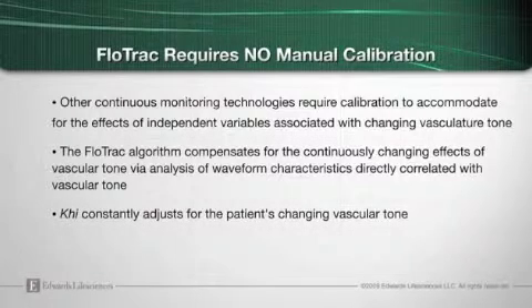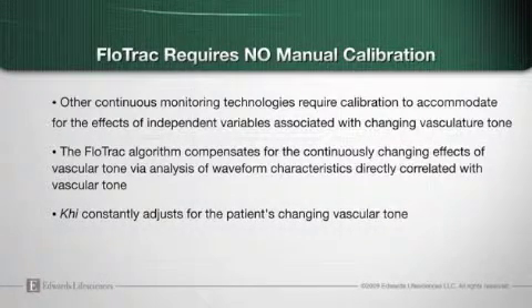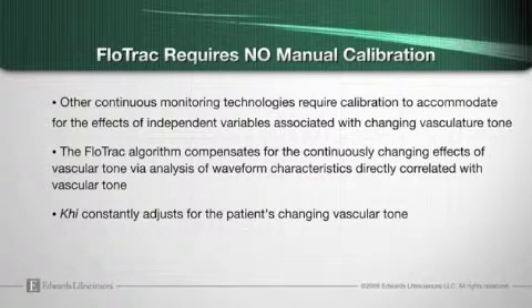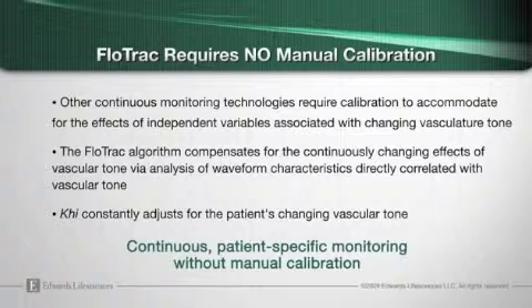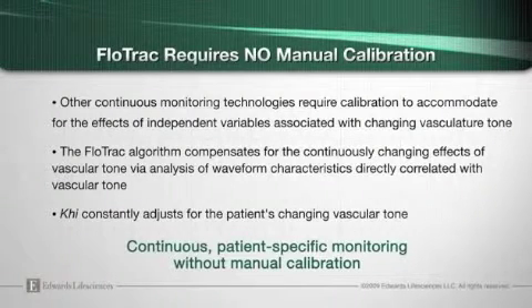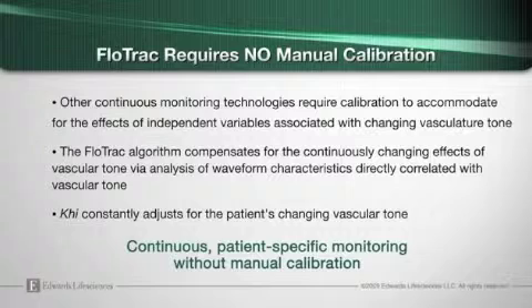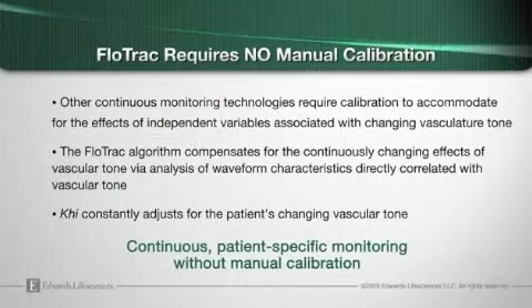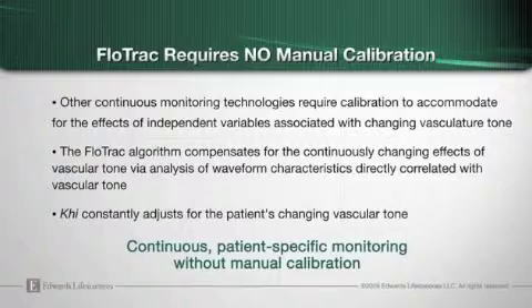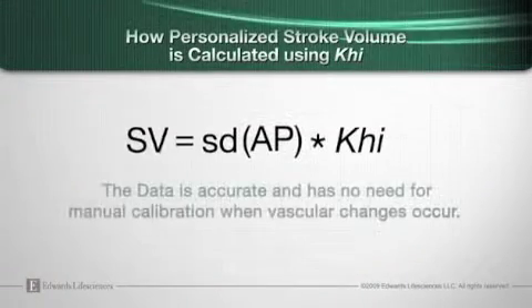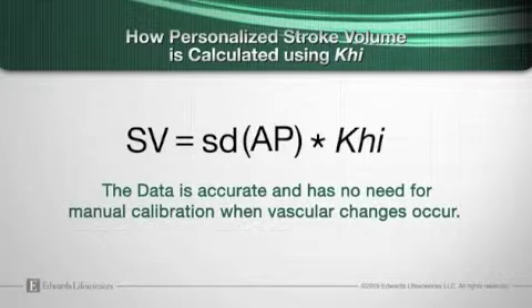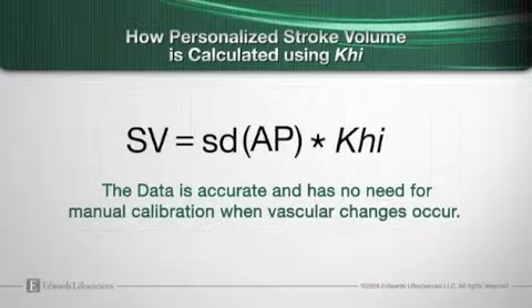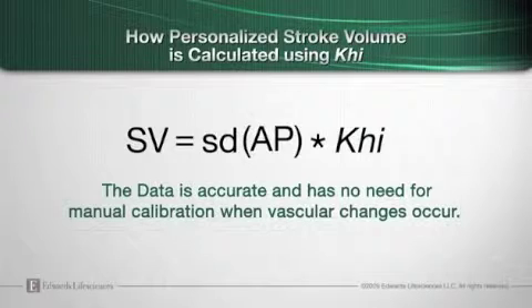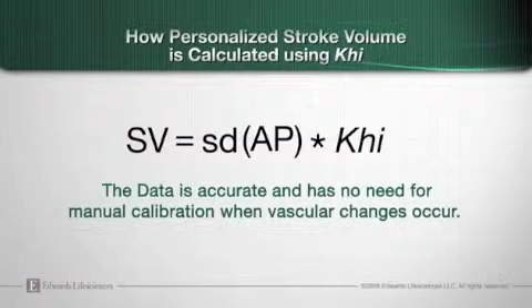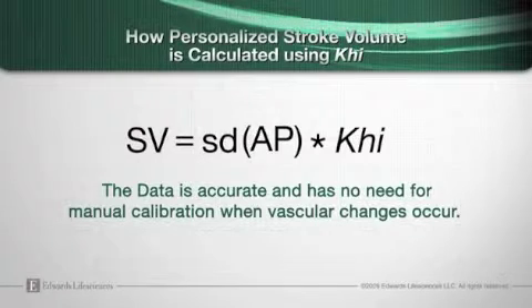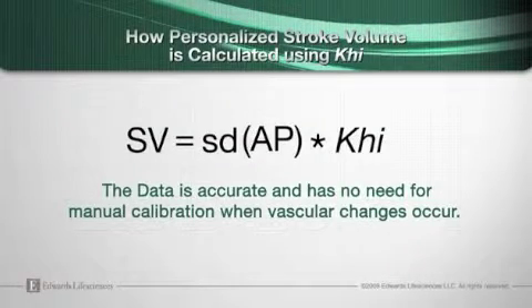By utilizing these empirical data relationships established during the development of the algorithm, the system is able to correlate pressure calculations with stroke volume without requiring a manual process of calibration, for example thermodilution or lithium dilution washout curve, and remains accurate when changes in tone occur. Other pulse contour or pulse power-based technologies require a dilution washout curve to provide a calibration constant, compensating for these algorithms' inability to independently assess the ever-changing effects of vascular tone on stroke volume.